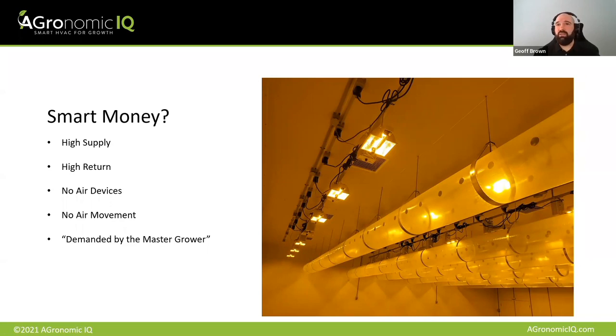They've got no air devices in the room to mix the room in any way. So in general terms, I'm not a fan of air rotation fans in a space. They basically are energy pigs. They're not particularly efficient at moving air around, and they tend to be applied more universally than they ought to be. You can achieve good air movement in the space just with good ductwork design, and not have that energy penalty of that extra set of fans.